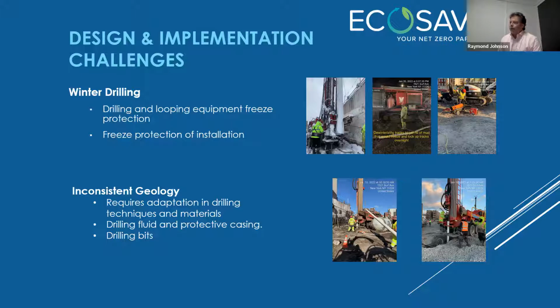The other thing that's so important with bore fields is to know the geology - not only the conductivity and diffusivity so you can thermally size the bore fields, but you've got to know what the soil structure is, what's underground. Is it clay? Is it gravel? Is it bedrock? Is it sand? What we found, even with test wells, is that it was inconsistent in places, and you have to be able to address that.